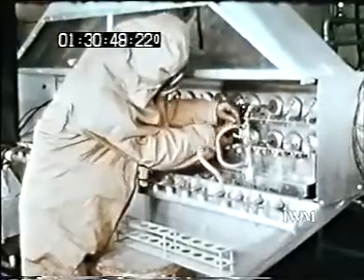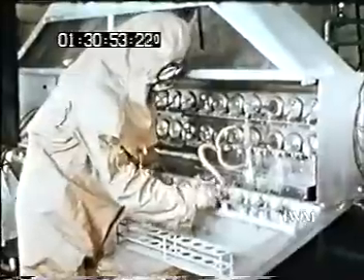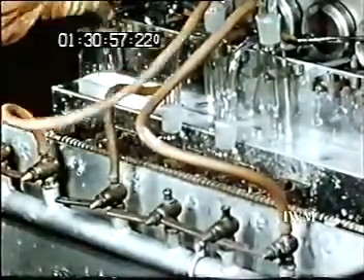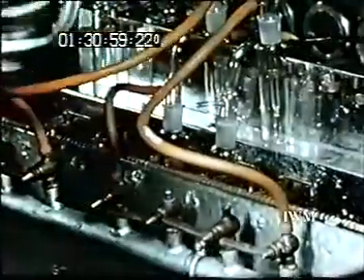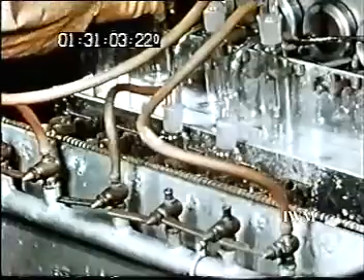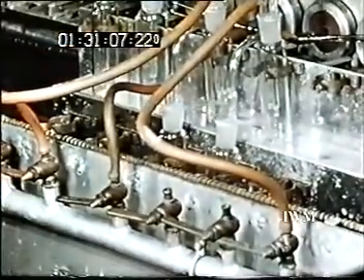Aerosols can be maintained in the sphere for at least 24 hours. Samples are obtained by applying a negative pressure to the samplers for a given time and at a given flow rate. The number of viable microorganisms per litre of air will be determined from the subsequent assay of the number collected in the sample.